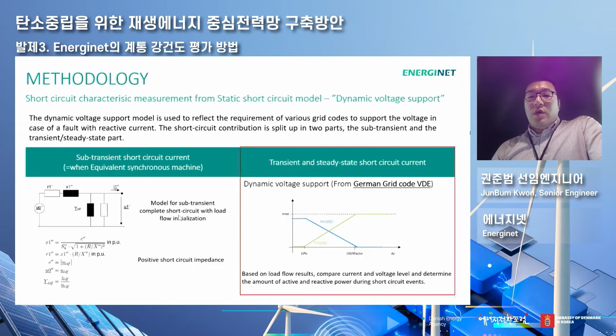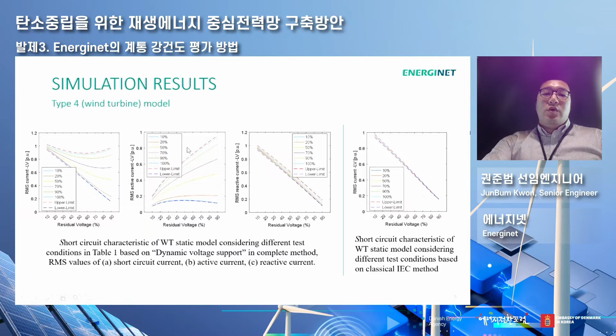Now this one is a simulation result. We first used only the IEC methodology, and when we do that, we try to compare what the contributions of the inverter are, and also what happens when we do that in parallel with the complete method. So for wind and PV, the contributions to the short circuit can be exactly and precisely calculated. You can see here the type 4 wind turbine model comparison between EMT and static models, and based on the complete model, we have done the simulations.